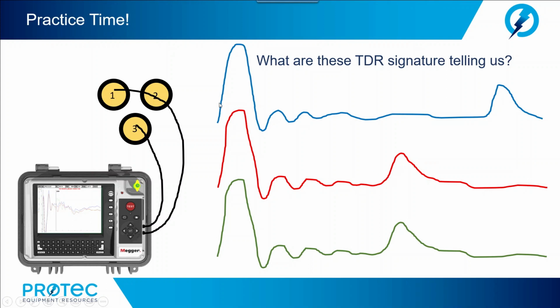So when connecting between conductors 2 and 3, we see an open circuit. When we connect from conductor 3 to conductor 1, we also see an open circuit at the same location.